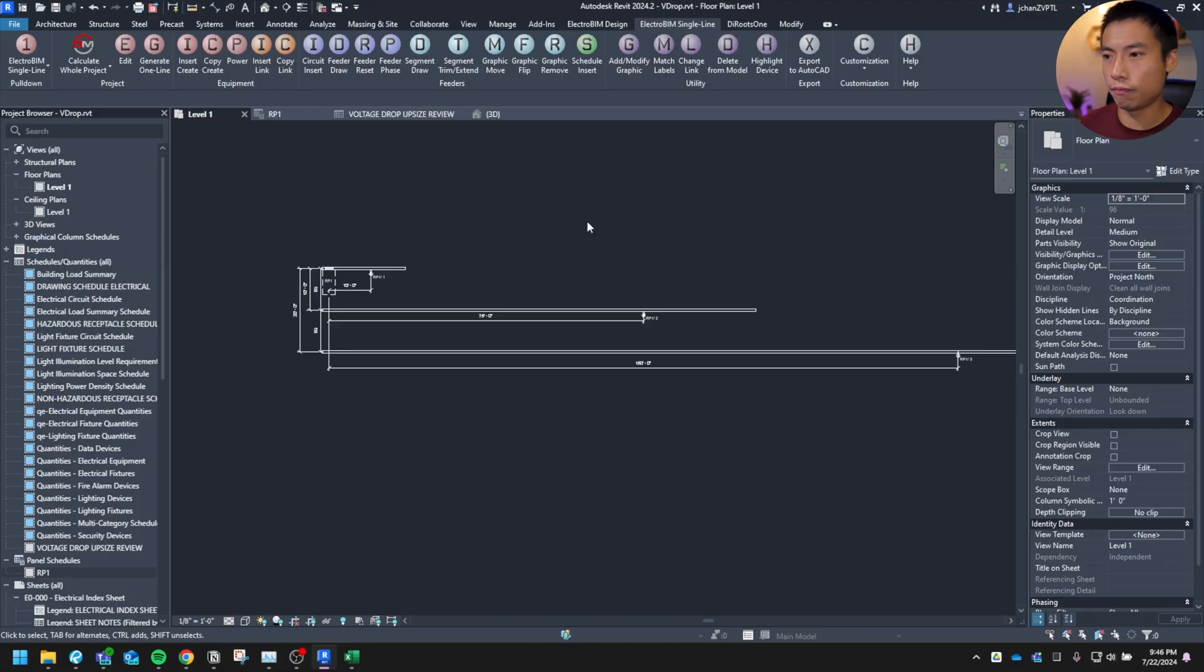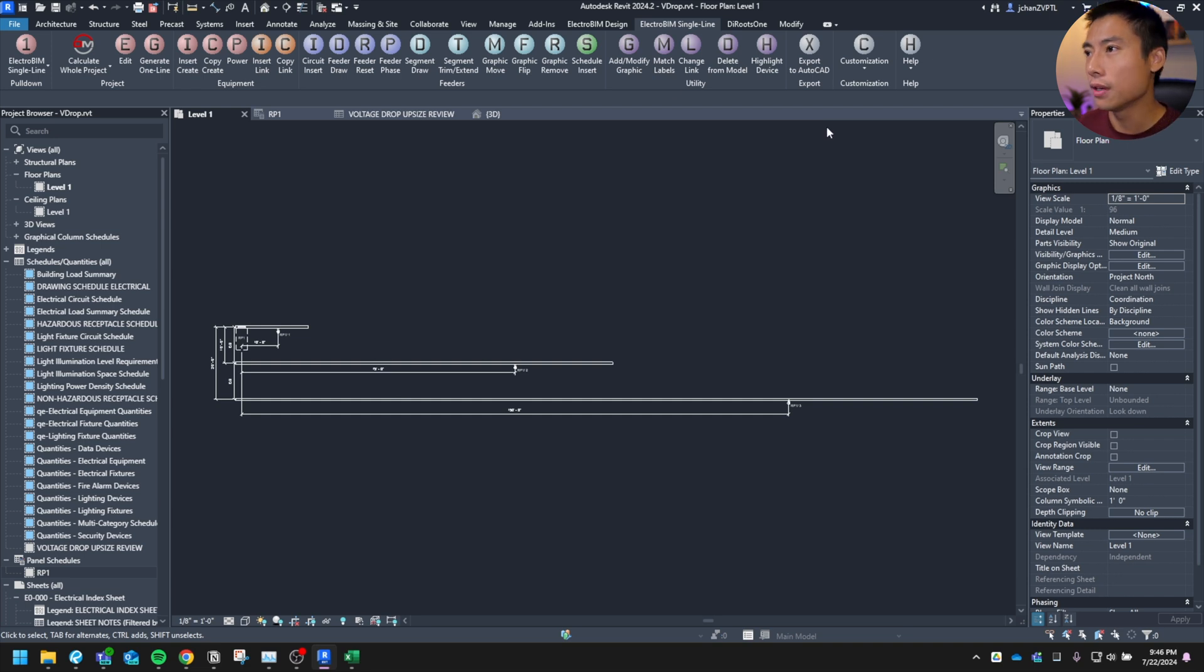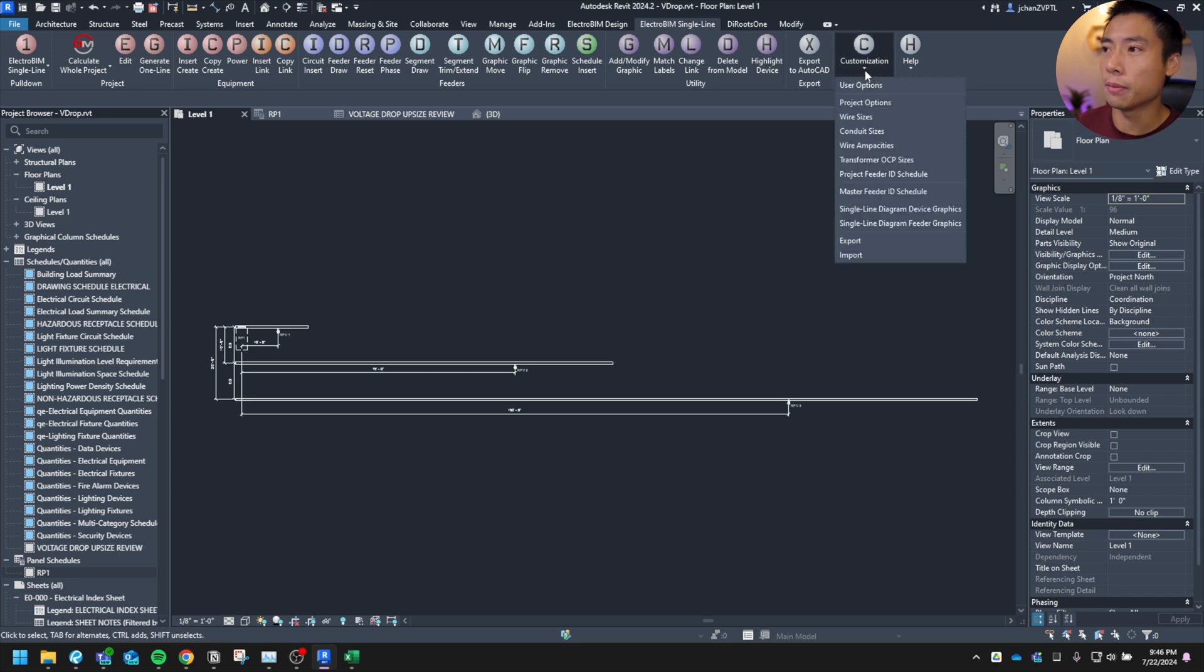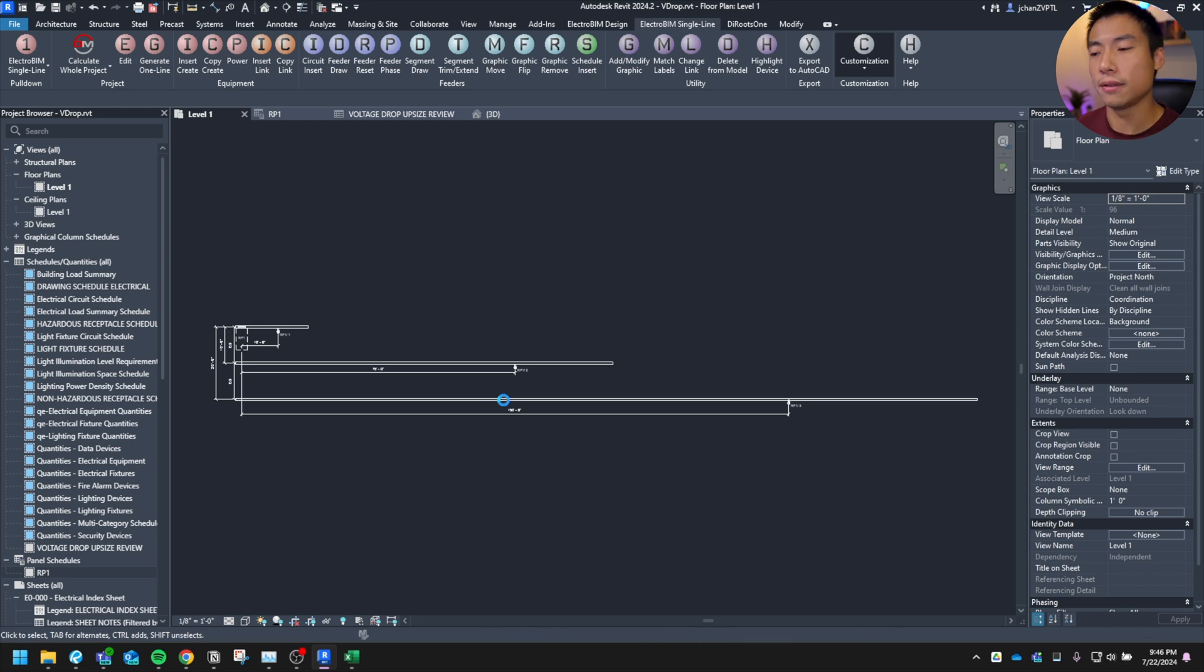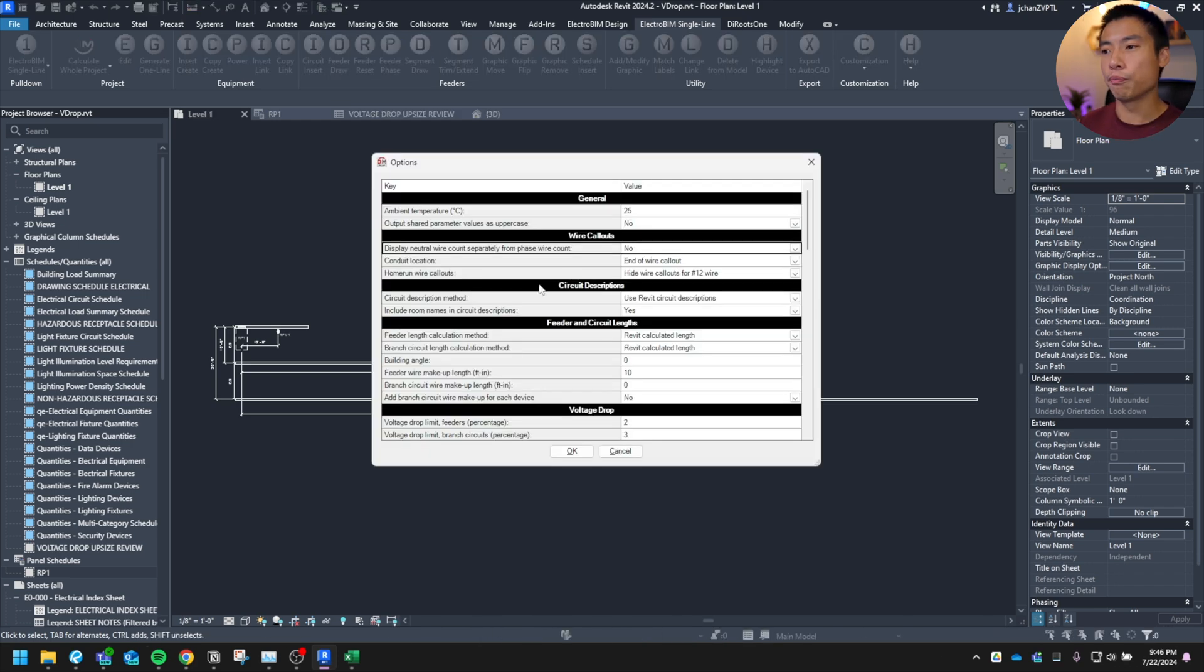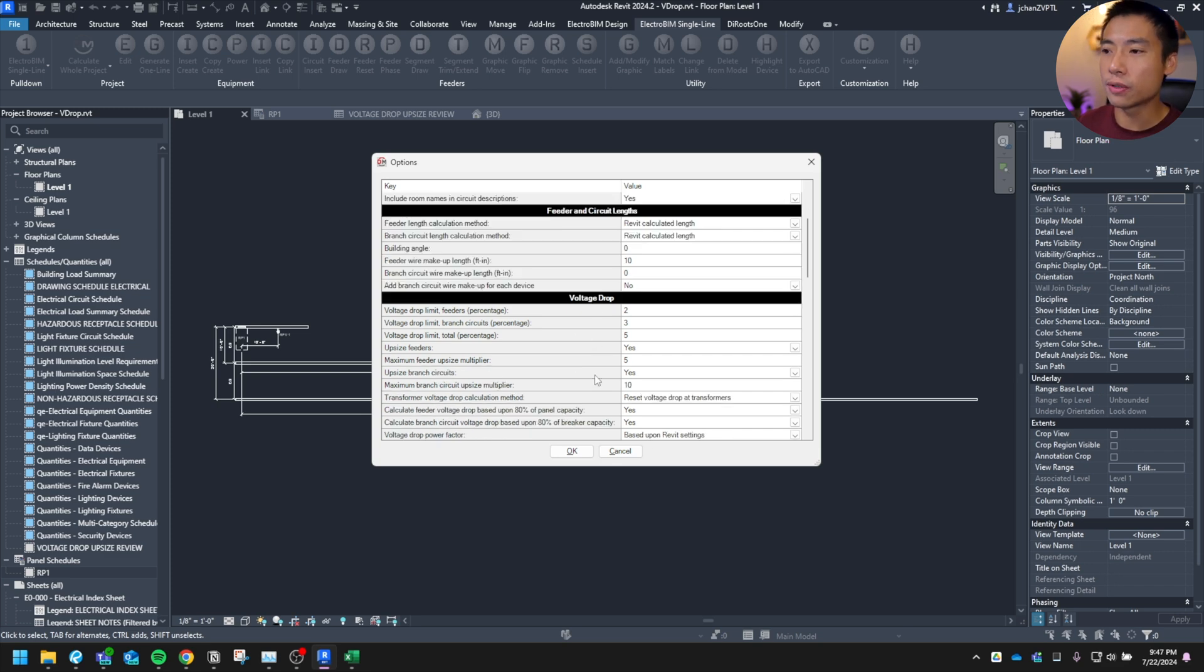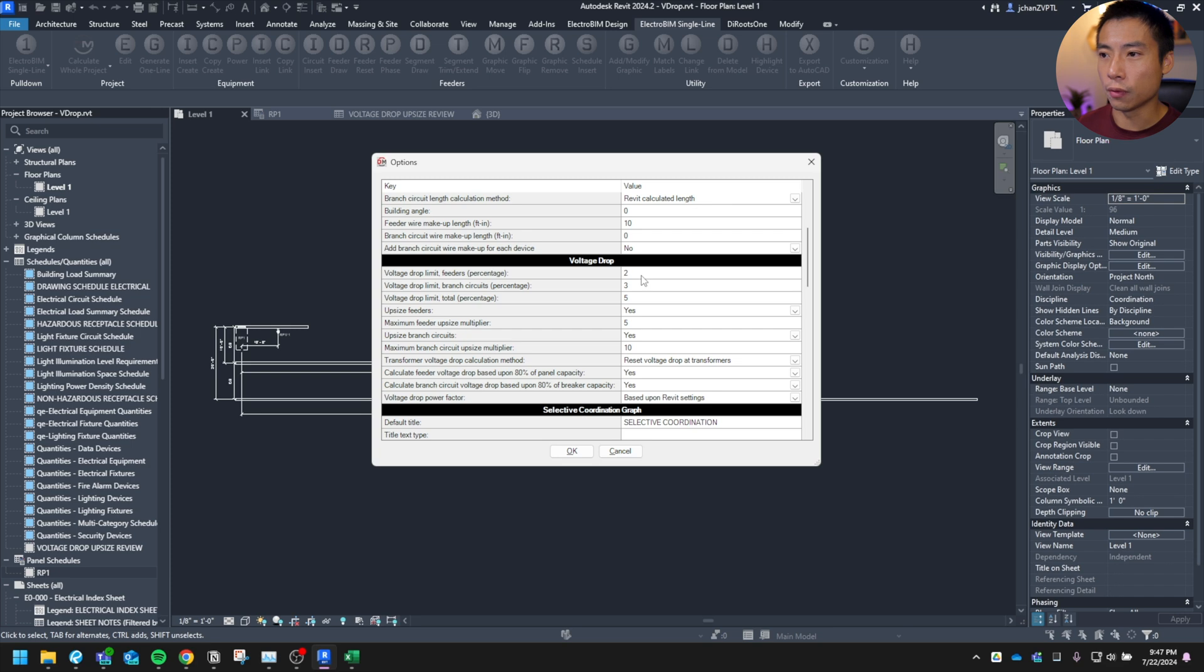ElectroBIM actually has a cool feature that lets you calculate the wire size for 80% load, but not necessarily force you to put 80% loading into your schedule. So let me show you how ElectroBIM's software helps. So for the customization, if you go under the ElectroBIM's tab and you go to customize under your project options, there's a couple things that you can tweak here, which is really cool. All right. So you might've seen this before in a previous video, but there's a new section down here for voltage drop.